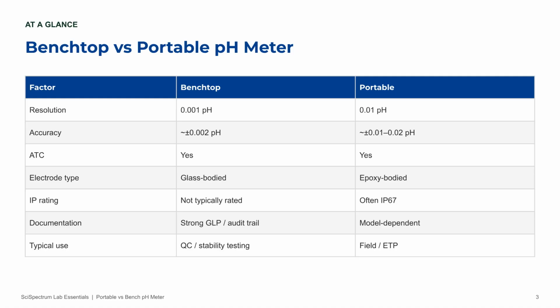Let's put both side by side so you can see the full picture at a glance. Benchtop gives you tighter resolution, 0.001 pH versus 0.01 on a portable, and it typically comes with stronger documentation. Portable wins on IP rating, and it's built for field and ETP work. Keep this table in mind, because we're going to unpack almost every row of it over the next few minutes.